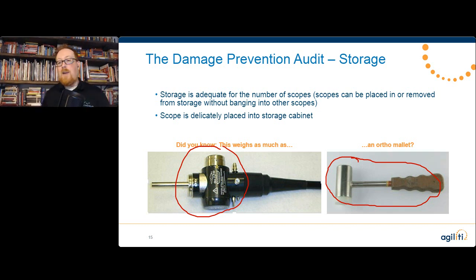But guess what? Every time we are in a hurry and we put a scope into the storage cabinet, or we take a scope out from the storage cabinet, and all those other scopes are swinging around and banging into each other, that's the exact same thing. That orthopedic mallet is swinging around. And guess what? Especially on colonoscopes, that light guide connector hangs at almost the exact same height as that distal tip where the CCD camera is, right? Who wins between the orthopedic mallet and the $6,000 camera that's the size of a grain of rice? Ta-da! The orthopedic mallet every time, right? So we have to make sure that we've got the right storage, there's enough space, and that we're not cramming a whole bunch of scopes into a storage cabinet that is way too small.